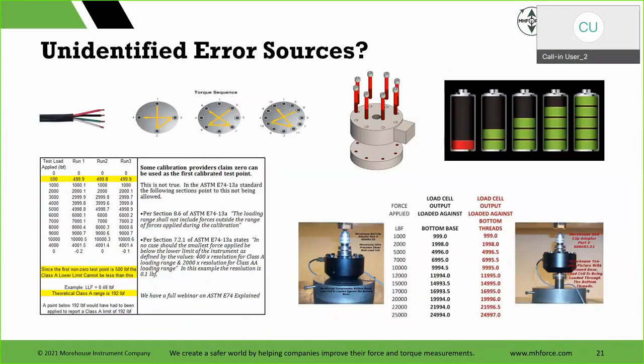And here's where we see common error sources for force calibration, including not replicating via calibration how the equipment is used. That is the number one. You don't talk to your customer and you assume something, and then you find out they're using it differently. Now risk is passed to them. Now they're making bad measurements. What if they're making measurements for auto brakes? We've had this happen. They have a load cell.